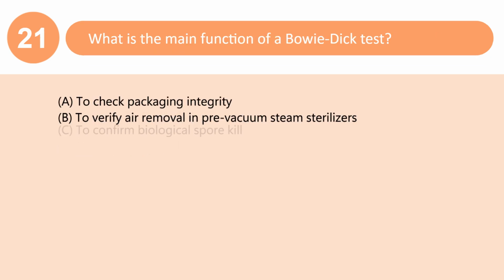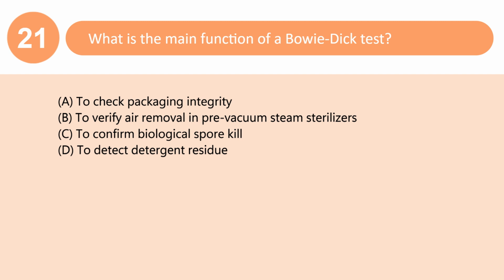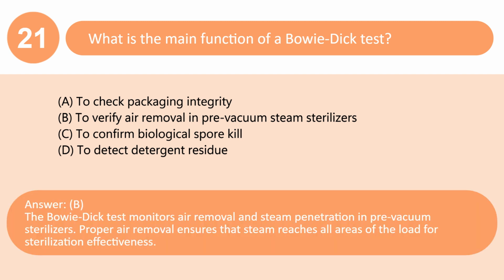What is the main function of a Bowie-Dick test? A. To check packaging integrity. B. To verify air removal in pre-vacuum steam sterilizers. C. To confirm biological spore kill. D. To detect detergent residue. Answer: B. The Bowie-Dick test monitors air removal and steam penetration in pre-vacuum sterilizers. Proper air removal ensures that steam reaches all areas of the load for sterilization effectiveness.